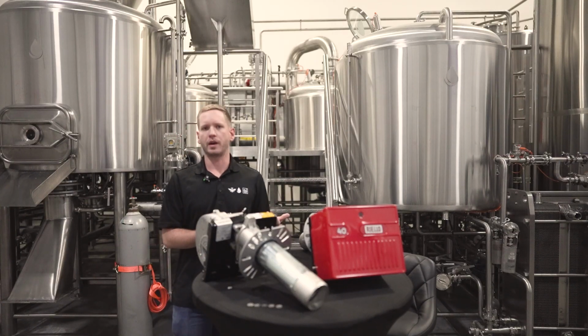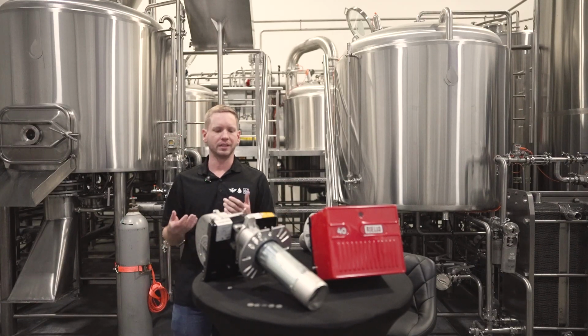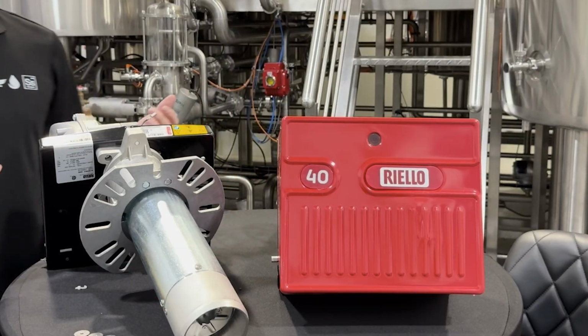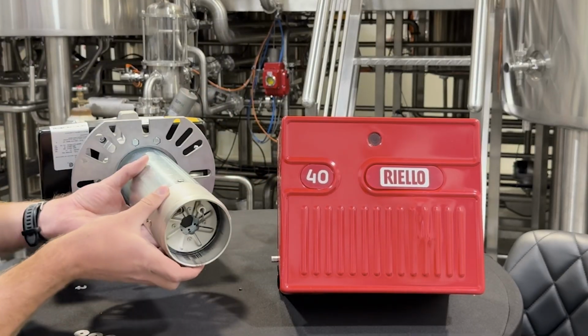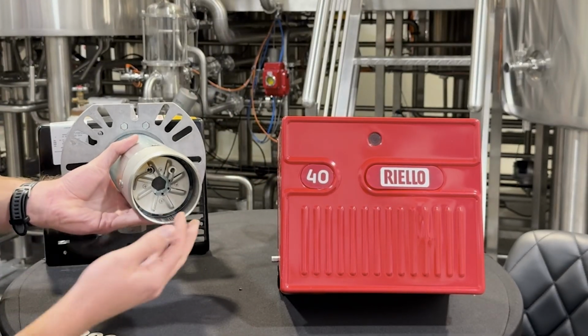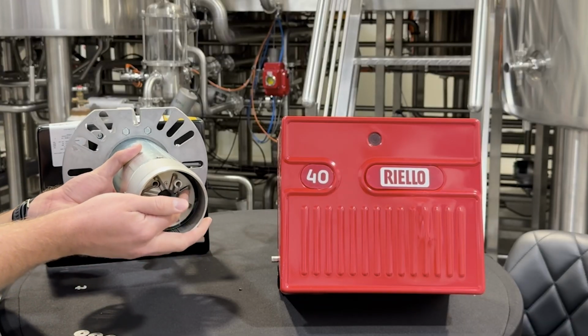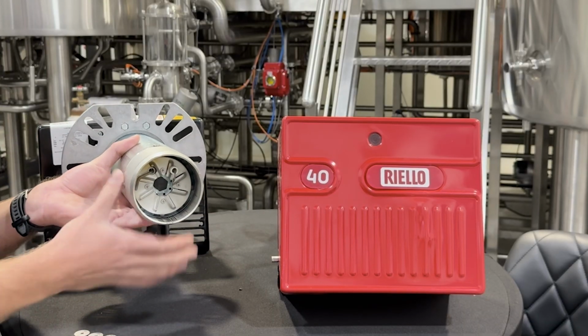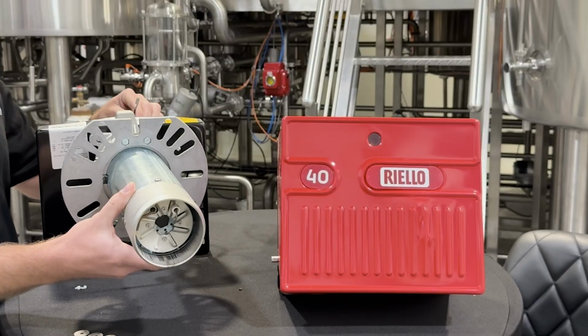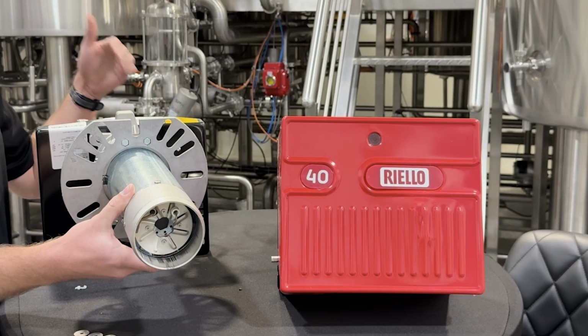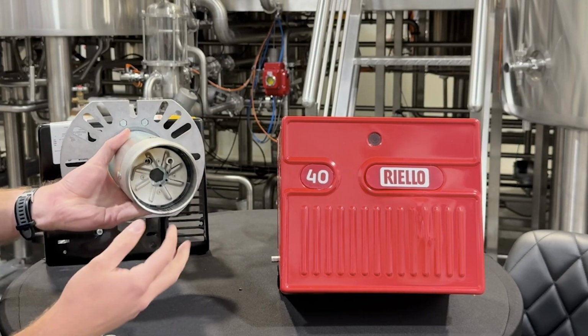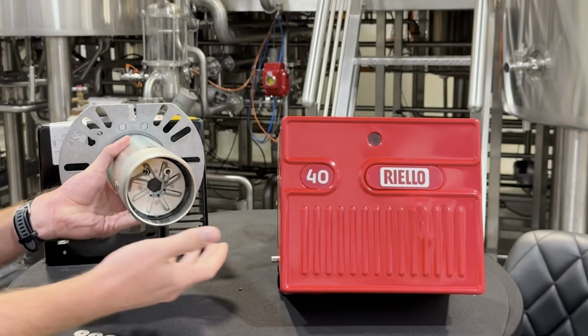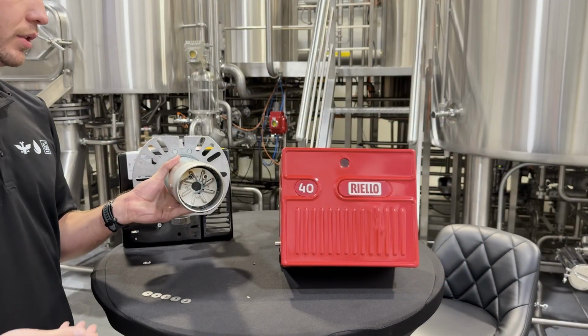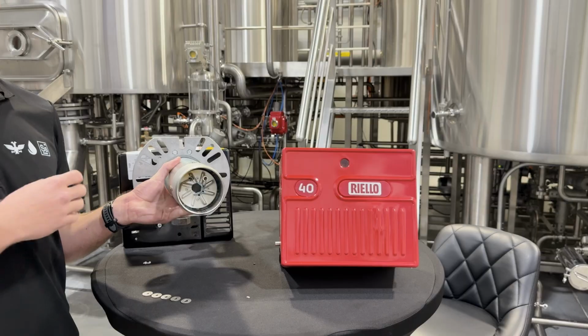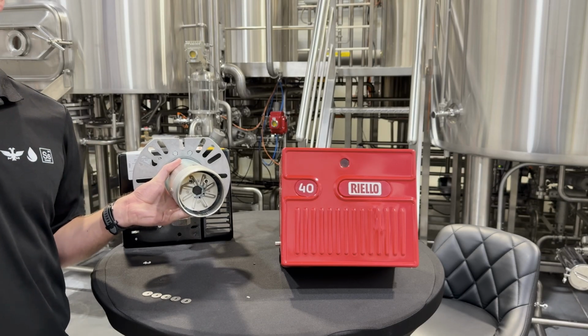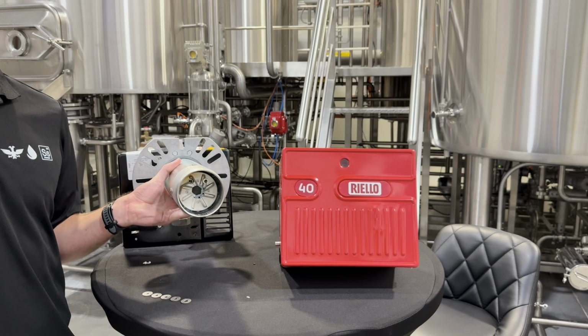If for whatever reason you're having a larger issue and you feel as though it is an electrical issue, on each burner we have an ionization and an ignition probe. Our ignition probe is right here. That's actually what's igniting the flame. There is a spark from a contactor here on the back. I'll flip it around in a second. There is a contactor on here that is generating a spark between this ignition probe and the front plate of the burner itself. That is what generates the flame, and of course your natural gas is going through and providing fuel to that flame.